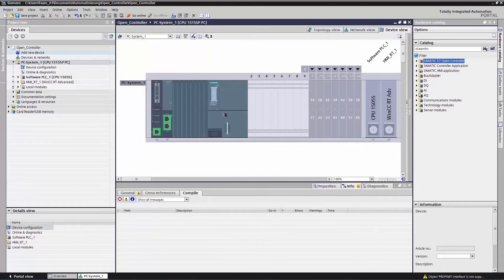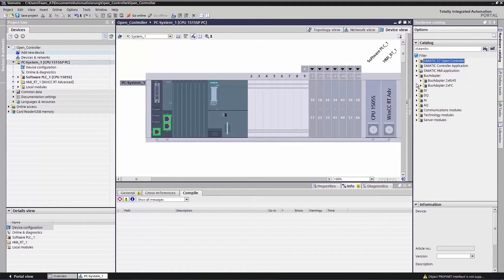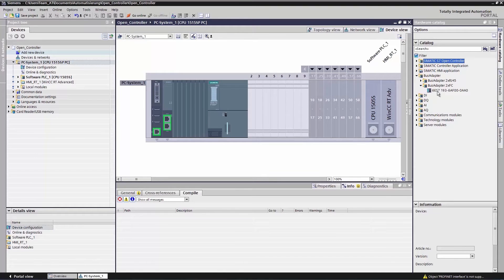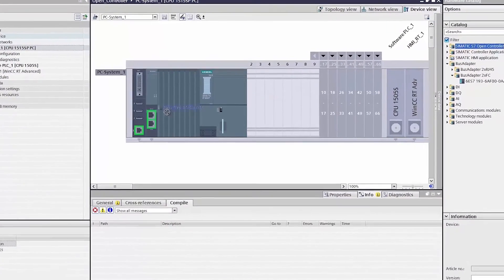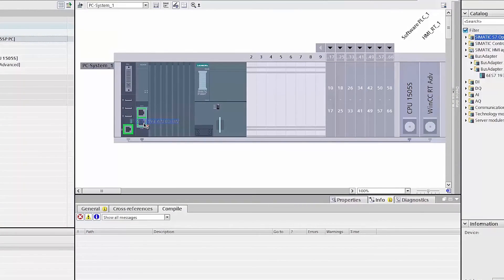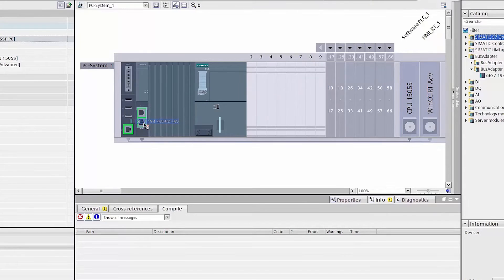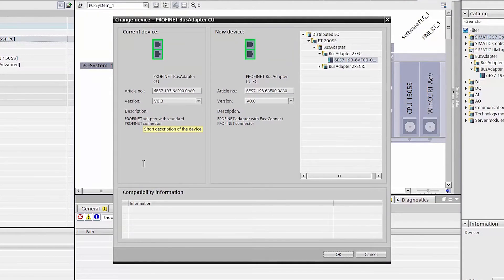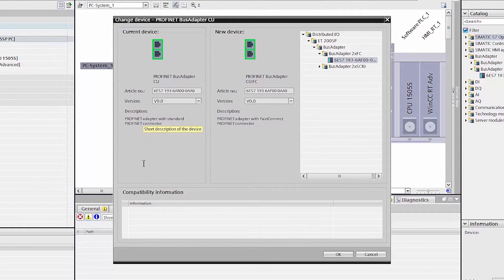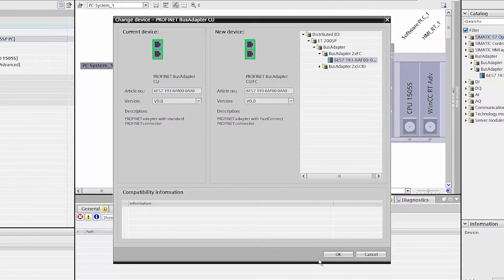The bus adapter is configured as an RJ45 model as standard. This will have to be changed if you are using the Fast Connect model. Select the Fast Connect bus adapter from the hardware catalog and drag and drop it onto the configured bus adapter. You will now see a small icon above the arrow, which should allow you to access the replacement dialog. We will now release the mouse button and a dialog opens in which you will see the currently configured bus adapter vis-à-vis the new bus adapter. Clicking OK will configure the Fast Connect bus adapter.